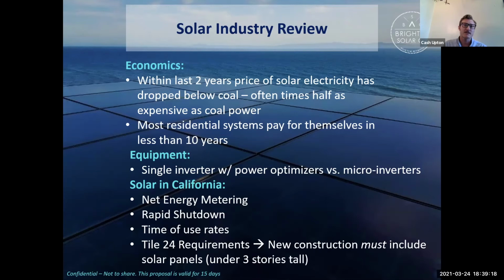One other thing is California has a law called rapid shutdown, to protect our first responders and workers, Edison workers. Essentially, when the power gets cut from the grid from Edison at any time, or the meter gets disconnected, the solar panels have to shut down at the module level. The reason is so they're not backfeeding electricity into an open grid where a worker could get electrocuted repairing a down power line, and also so a firefighter cutting a hole in the roof isn't hitting a conduit with solar electricity. Power optimizers and microinverters allow for that rapid shutdown at the module level, whereas normally the shutdown would have to happen at the inverter or the meter. It gets a few customers annoyed because they can't have electricity during the day when the power goes out, but it's for a safety standpoint, and it really is necessary.